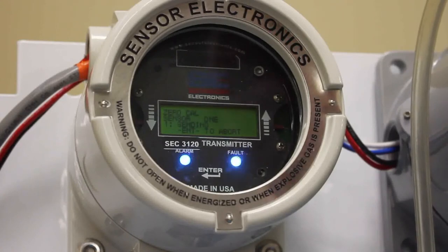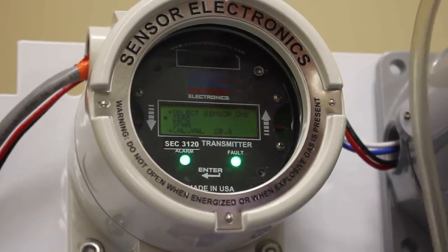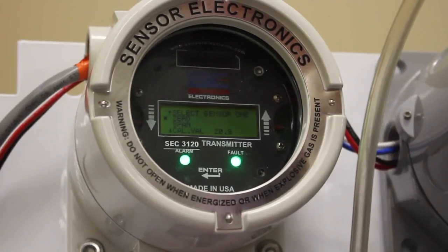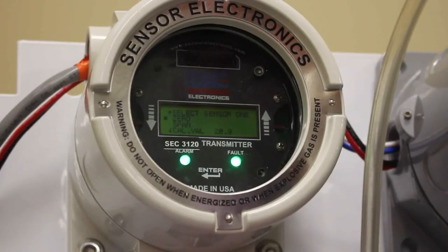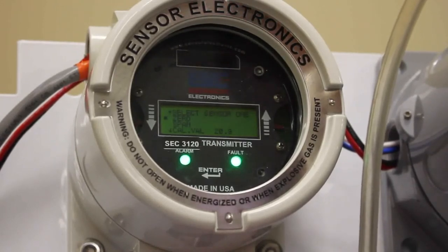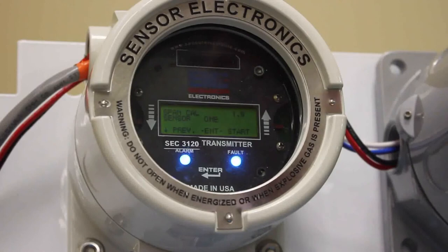So now the transmitter's zeroing the sensor to the nitrogen gas being applied to it. And it goes through its little calibration procedure. Once it's complete, it just uploads the date. And now the oxygen sensor is zeroed. So the next procedure would be to span the sensor. In this case, we'd have a cylinder of 20.9 calibration gas. Or we can just use the ambient air to calibrate the sensor as well.